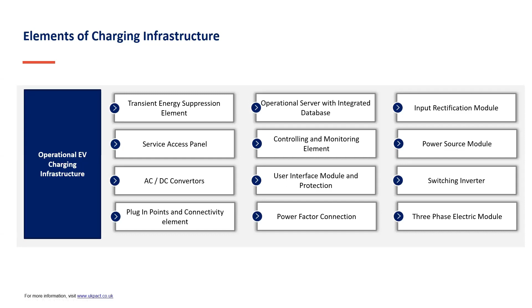And the power source: chargers typically take in power from the normal AC grid supply, either single phase 230 volts or 3-phase 415 volts. Irrespective of the type of charger, AC or DC, the power supply source is from the grid. Of course, the grid could be the normal grid from the distribution utility, or it can be a solarized grid with a solar PV panel, and if required, sometimes storage as well. So solar plus storage could be the source of supply. But electrically speaking, the chargers get input at AC, either single phase or 3-phase.